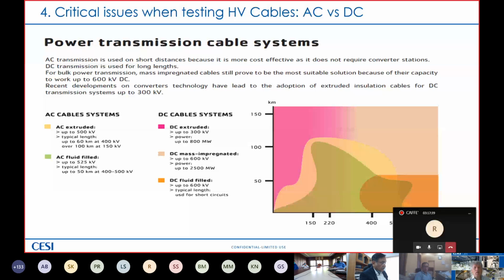I use this picture to give you some idea of the cable length of the interconnections that normally apply for the use of AC versus DC, and also the voltage level with the insulation material that is used, comparing AC extruded and AC fluid filled, or DC extruded, DC mass impregnated and DC fluid filled. You can see that with interconnections longer than 130 kilometers, it really depends from project to project and the cost associated.